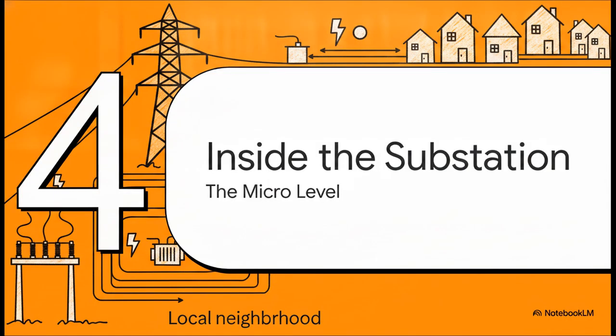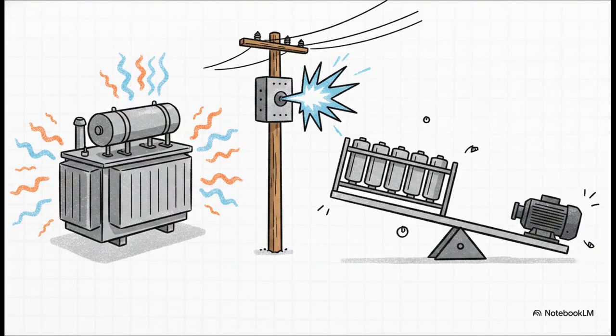Inside the substation, let's zoom all the way into the micro level. Inside these facilities, transformers step voltages down, and smart reclosers act as self-resetting breakers. But the real high-stakes math happens with capacitors, and this all comes down to the power triangle. You see, apparent power, represented by the letter S, equals real power, P, plus reactive power, Q.